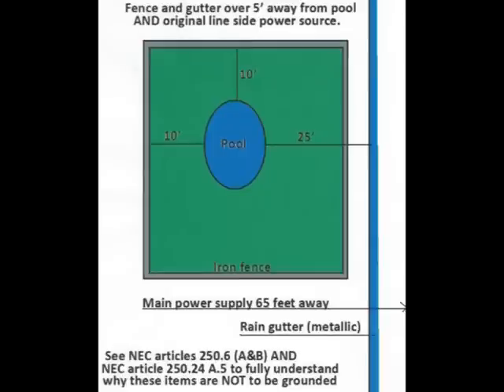What is it? It is a current that would not normally be found, which is a hazard. And how does it occur? It usually occurs when a metal object that is not required by code to be grounded is grounded to a main power source. If there is a fault in the main power feed and goes to ground, then every item grounded to that source becomes energized. A key word here is potential.